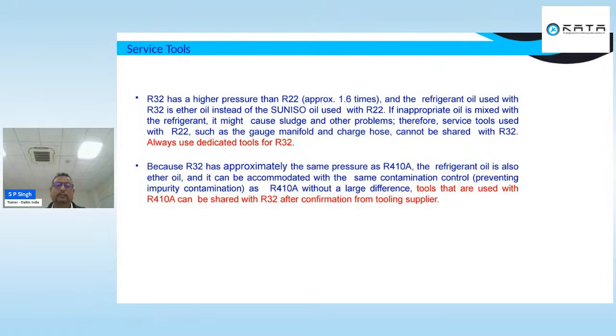So here you can see that R32's pressure is almost 1.6 times higher than R22. And the grading of the oil is different for R32, for R22, and even for 410. Though the refrigerant oil is a mixture with refrigerant, the viscosity of that particular component is different. That means impurities will again take place, so whenever we are charging, we should charge 410 with 410 tools and R32 with R32 tools. We should have this awareness so that no hazard takes place, and we give the same performance as what the new manufacturer has supplied at your place.